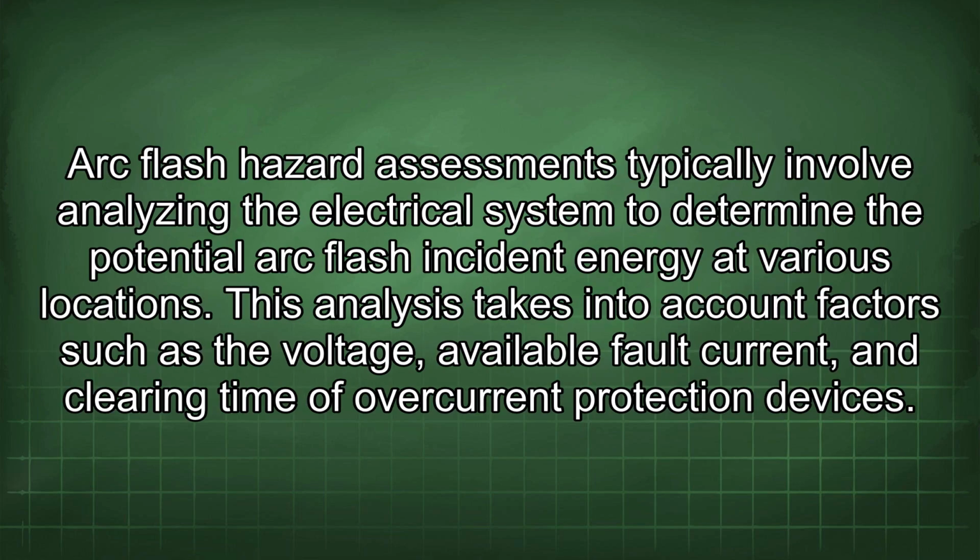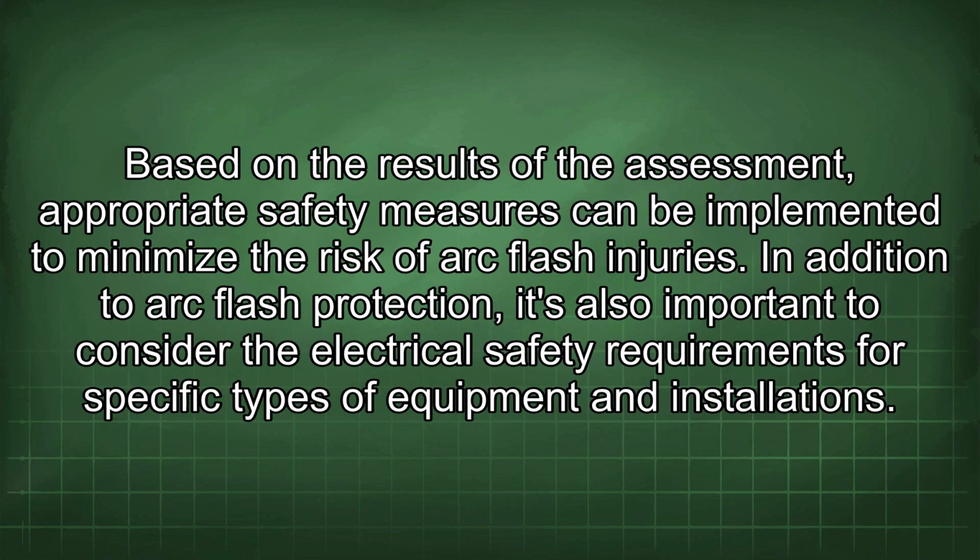Arc flash hazard assessments typically involve analyzing the electrical system to determine the potential arc flash incident energy at various locations. This analysis takes into account factors such as the voltage, available fault current, and clearing time of overcurrent protection devices. Based on the results of the assessment, appropriate safety measures can be implemented to minimize the risk of arc flash injuries.